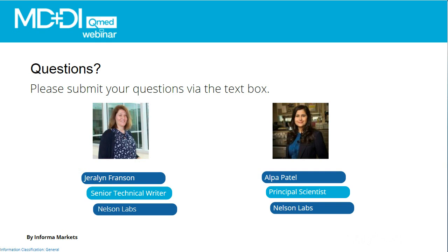With the upcoming changes in reporting acceptance criteria for cleaning validations, how will this affect our legacy products, or products that were validated before the standard is published? That's a very good question. We have a lot of legacy products out there, products that were validated a few years ago. With this new requirement, where you have to apply the standard deviation to the test replicates and apply it to the highest test result, you would have to go back and make sure that the test replicates you received for your product were within the specification.